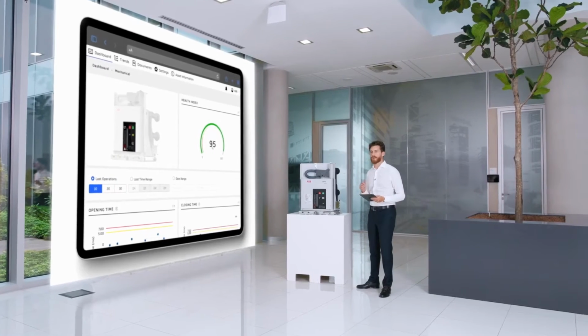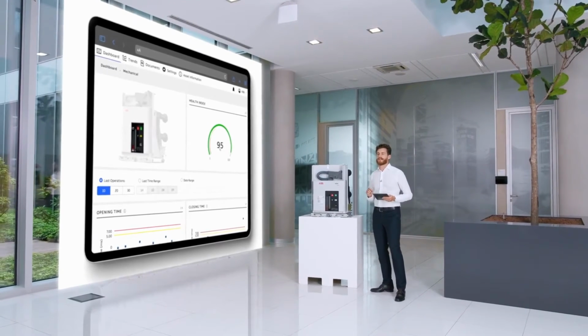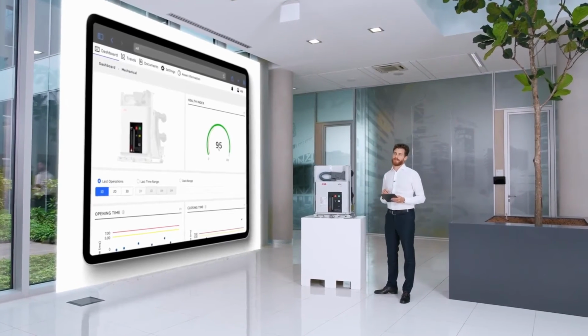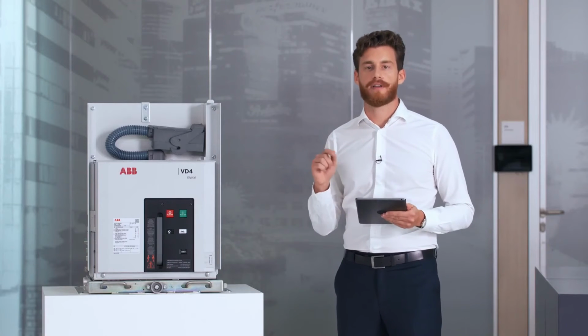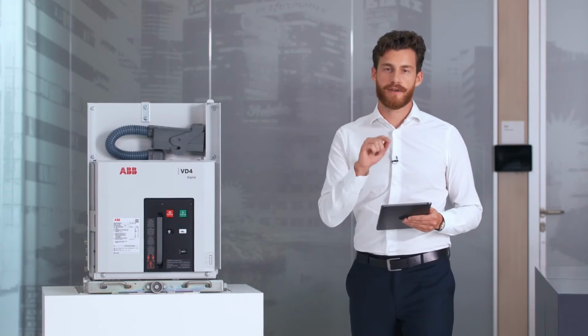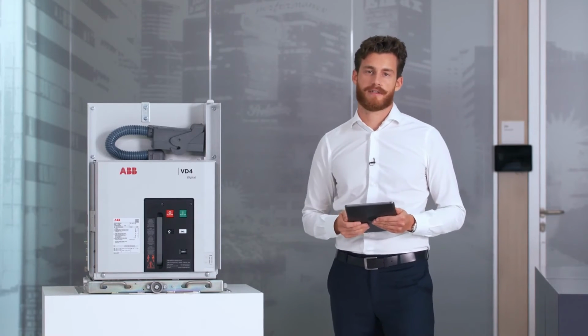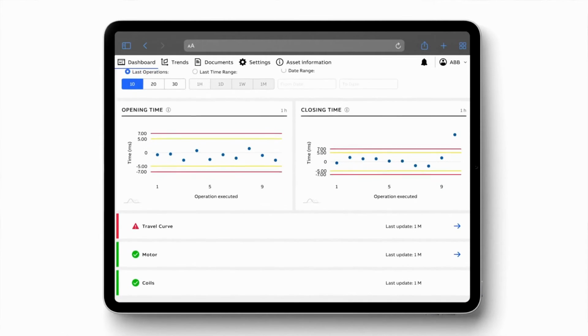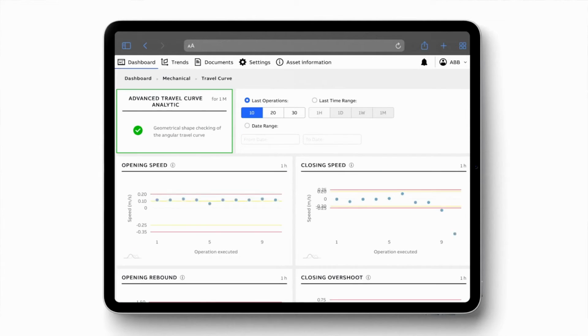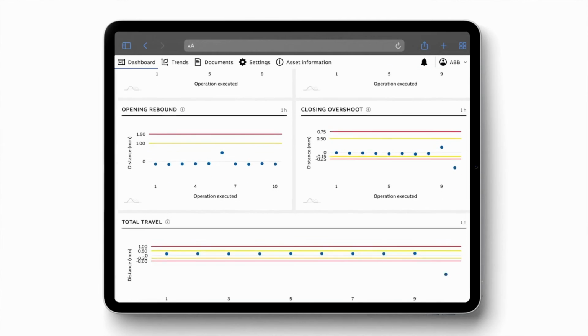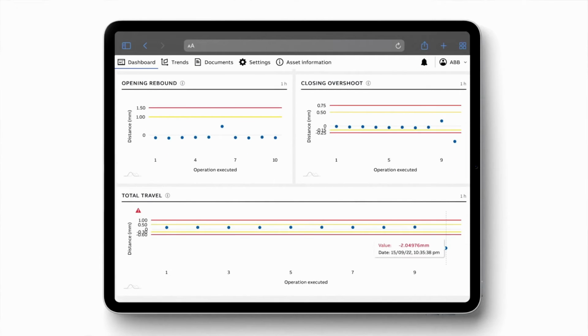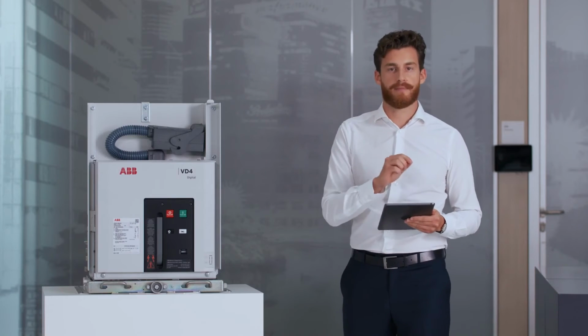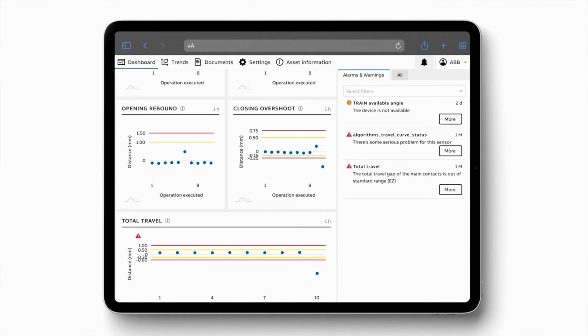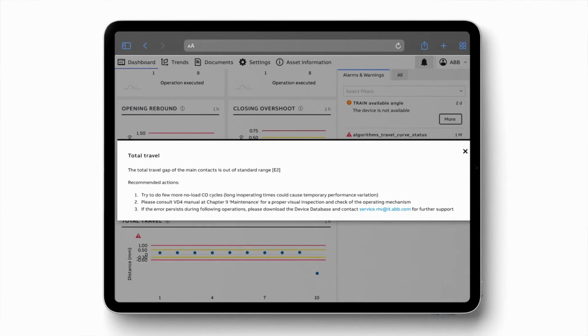With VD4 Evo, however, the check is relentlessly done on each breaker operation, and all the parameters are benchmarked against the proper design references specific to the single unit characteristics. In case of anomalies, we firstly indicate a possible root cause and suggested action, but there's also the option of directly contacting an expert in case of a permanent message, so to get a fast and focused solution in a few steps.